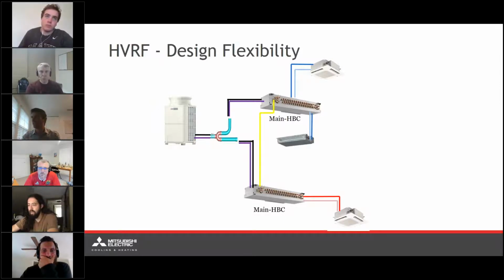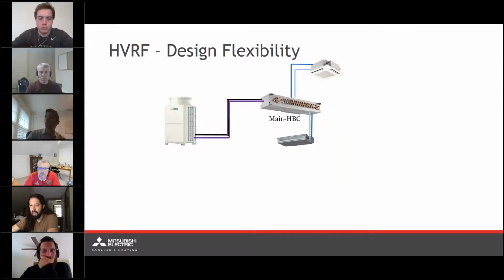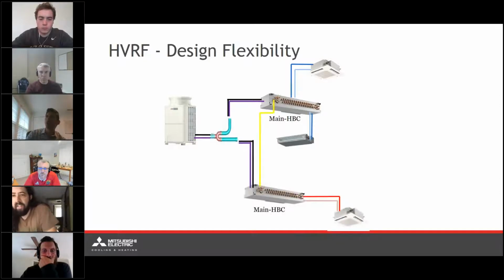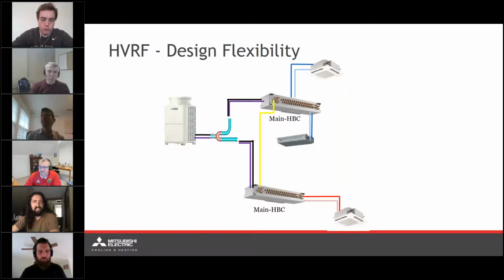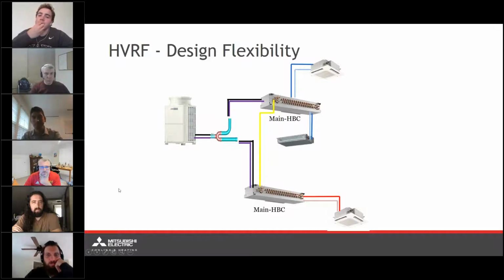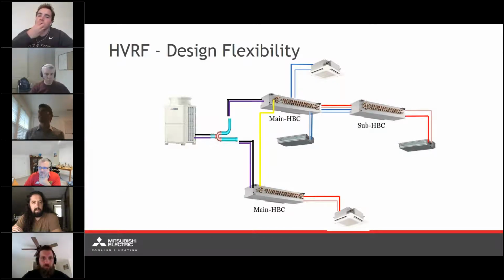So just to go through what we're looking at here from a piping standpoint, as opposed to just a single main HBC with 2 pipes going in, we're going to have splitting branch teeing off those refrigerant connections leading to both the main and the secondary main HBC. And then this yellow line in between is just going to be water piping, just balancing the water loops between the 2 systems. So again, this is just an example of how robust and broad this particular install could be.